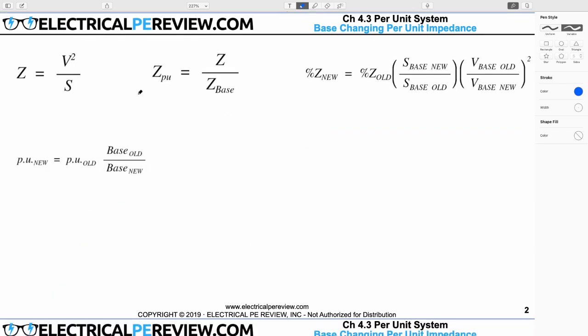Let's look at exactly how we do that. Here on your screen I've got a couple of things to introduce. First, remember that we can solve for impedance as V squared over S — this is your V squared over Z equals S formula solved for impedance. Next, it's important to remember that a per unit impedance, or percent impedance — same thing — is really your impedance value Z, which equals V squared over S, divided by your Z base, which is your base voltage squared divided by your base power. Here's our original base changing formula: our new per unit equals our old per unit times our old base divided by our new base. Let's use impedance terms and expand on this by inserting our V squared over S fractions.